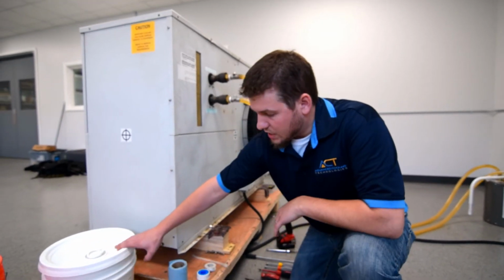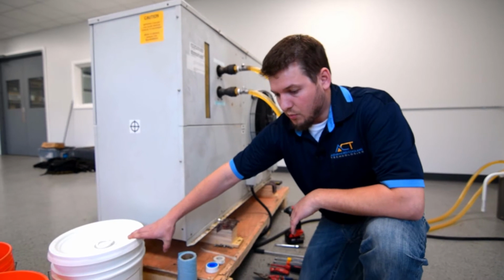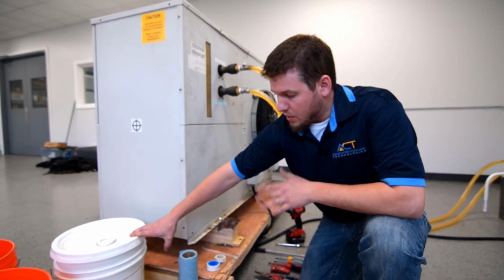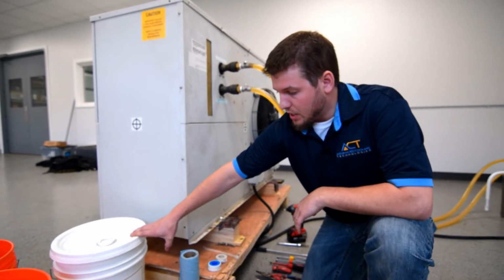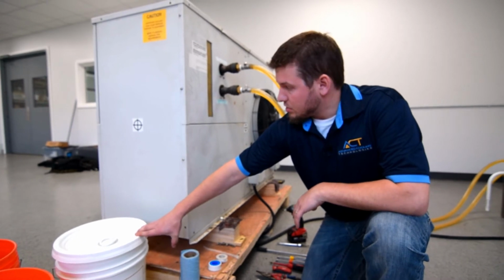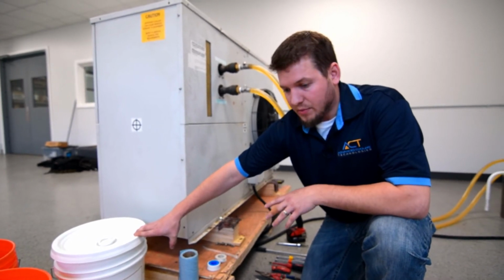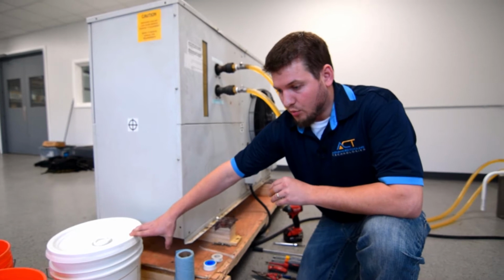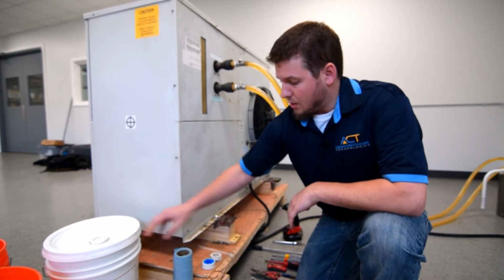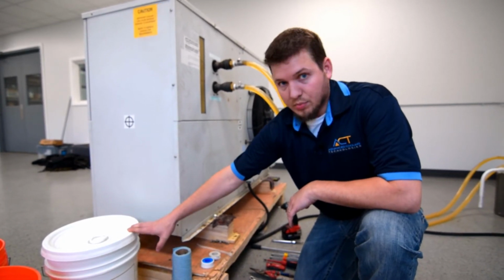It's also a good idea to bring glycol to the chiller for this repair. Here at ACT, we do supply OEM glycol, and what's required for these air assist chillers is a 50-50 mix of propylene glycol with a yellow rust dye inhibitor. If you have any questions about that, you can always call our sales department.